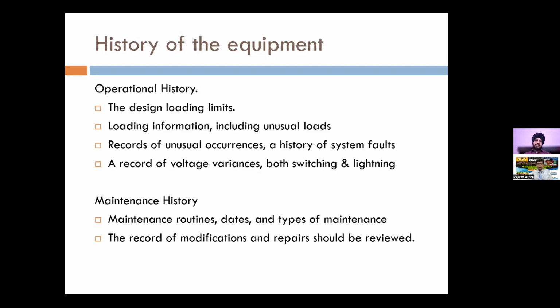Then should also consider the history of the equipment, as in the individual history of the equipment, the maintenance history, when, how frequently the maintenance is being done, and what were the earlier results of, let us say, if there has been a slow deterioration in oil parameters, which may indicate that moisture was slowly entering. So all this can be demonstrated by the maintenance history. And if there has been any recent modification and repair which has been done, which also could have caused or contributed to this failure, it should also be considered when you are establishing the root cause.